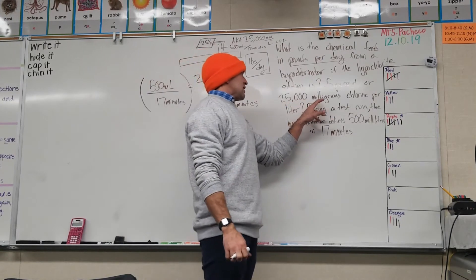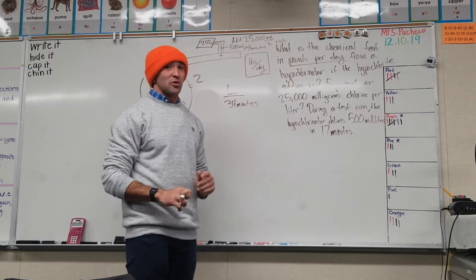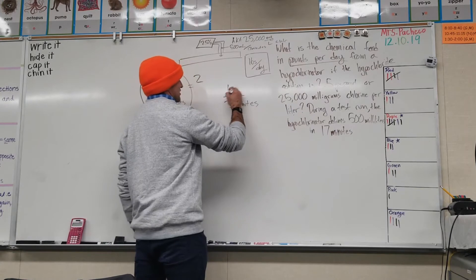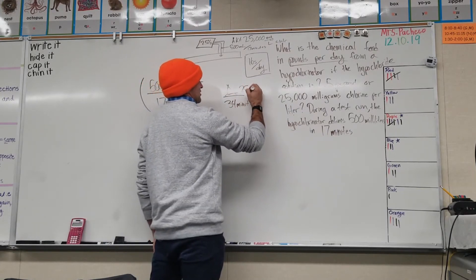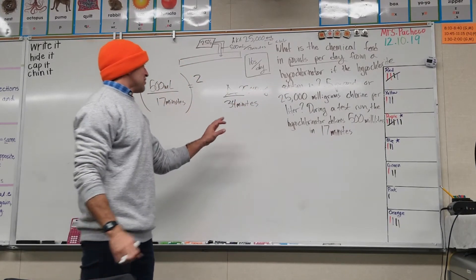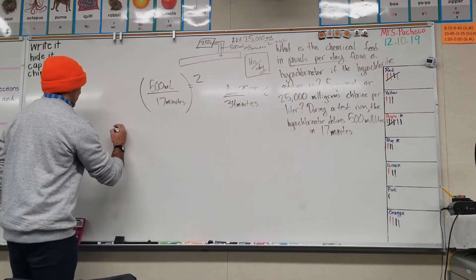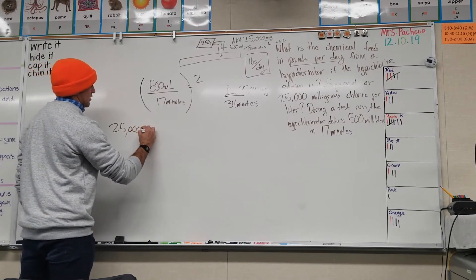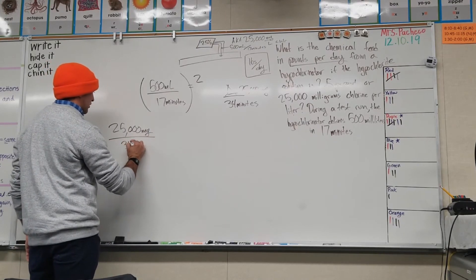We know there are 25,000 milligrams of chlorine in every liter. Since we now have one liter per 34 minutes, we can substitute: we have 25,000 milligrams per 34 minutes. Now we have weight over time. It's just a matter of converting this weight to pounds and this time to a day.